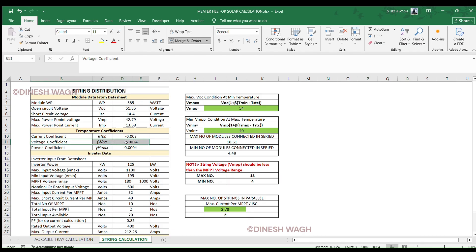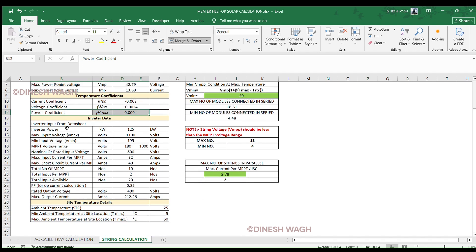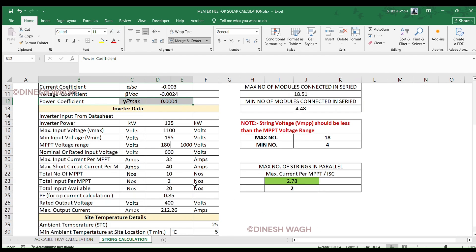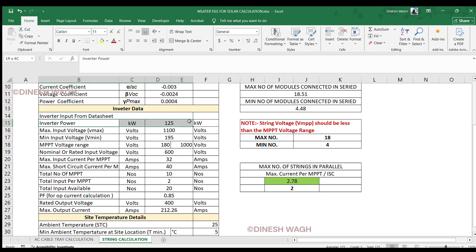These are used in voltage correction formulas for high and low ambient temperatures. In Part 3, we look at the inverter data. Let's check the inverter specifications, which are critical to string sizing. The inverter power we are considering is 125 kW — it's a Growatt inverter. I'm not doing any marketing for Growatt here.